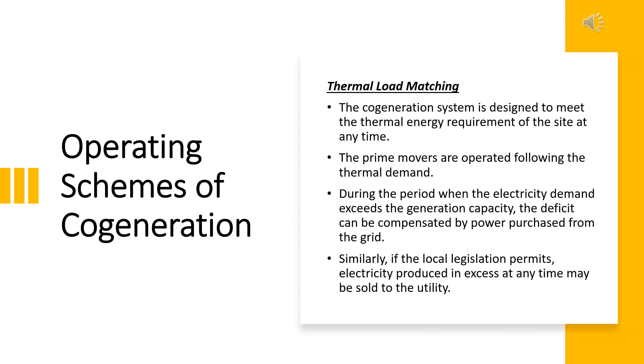The last scheme is thermal load matching. The co-generation system is designed to meet the thermal energy requirement of the site at any time. The prime mover is driven by thermal demand. During periods when electricity demand exceeds generation, the deficit can be compensated by power purchase from the grid. Similarly, if local legislation permits, electricity produced in excess may be sold to the utility.